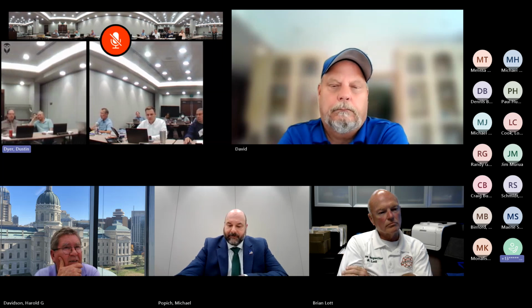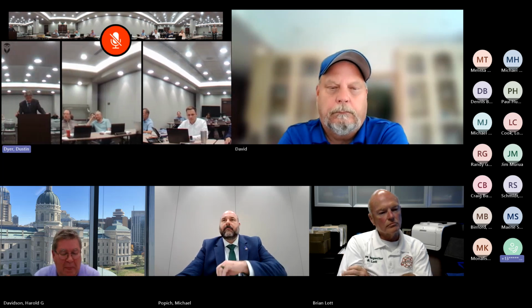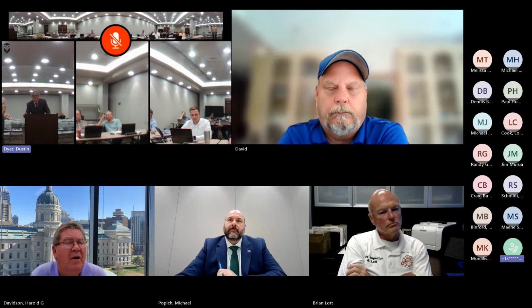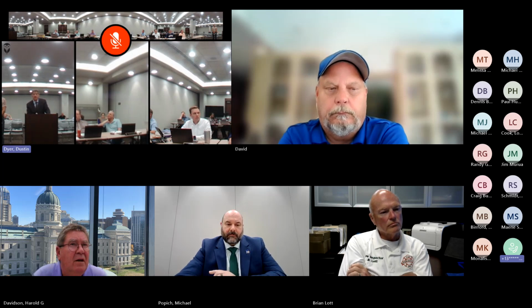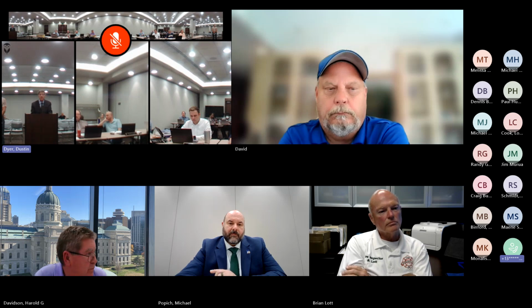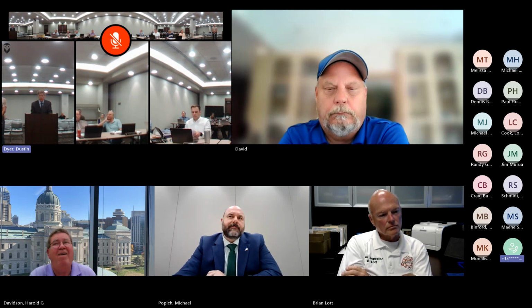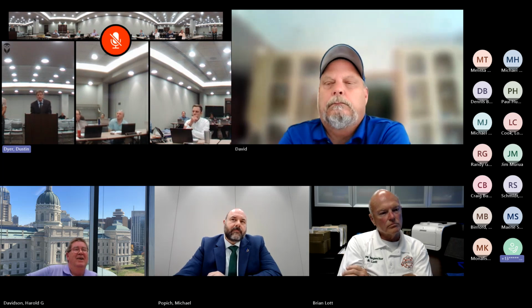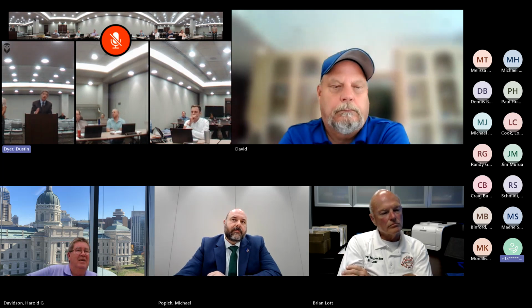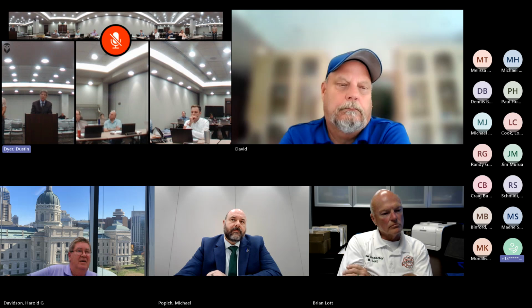If you're inclined to act on this tonight, can I suggest you approve it on the contingency that all standard response sprinklers be traded out for quick response? Because if you deny it outright, that means they have to change them all out, and there's no need to do that since about 40% are already quick response with 155-degree sprinklers. Run that by me one more time. So I'm going to suggest you approve the variance, but on the condition that all the standard response sprinklers be changed out to quick response.